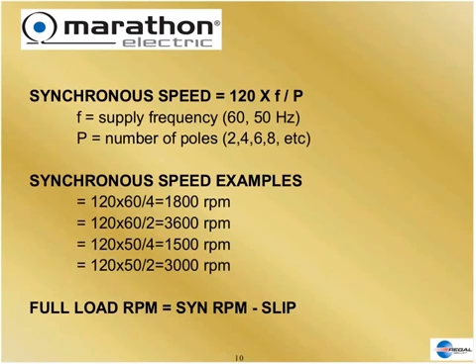Back to three phase: how fast is this wave going to move? It's going to move based on the frequency — the rise and fall of the waveform, how many cycles per second — and the number of poles we wind our motor with. We capture this wave into a circle, create north and south magnetic poles in that circle, and that wave travels around the circle at the speed called synchronous speed. Then we put a rotor in the middle, and the rotor will try to follow the wave around the circle, thus causing rotation.